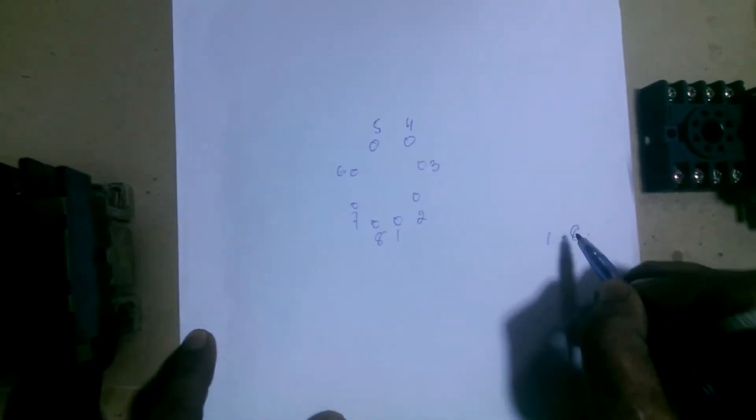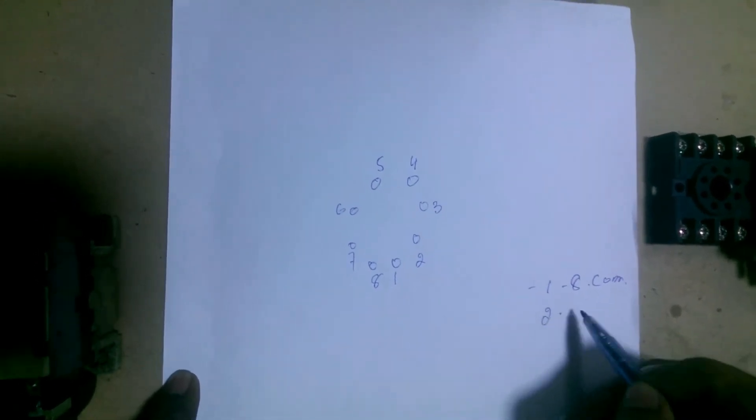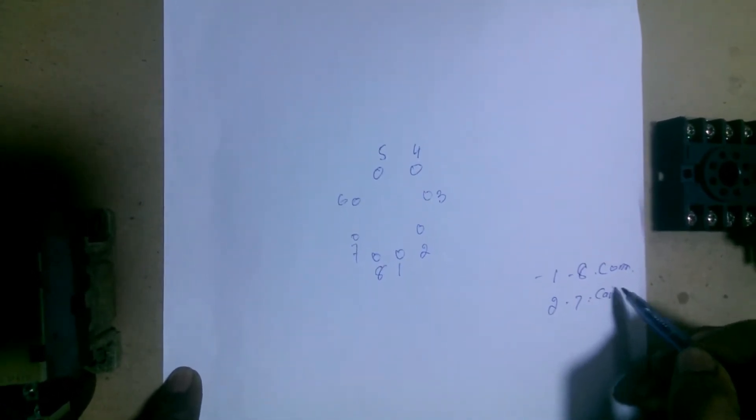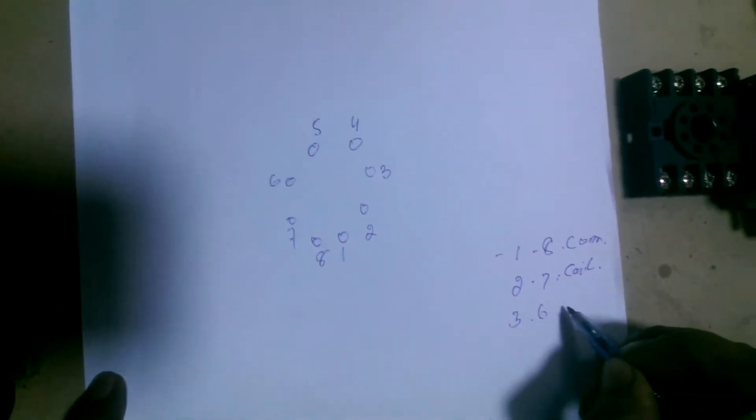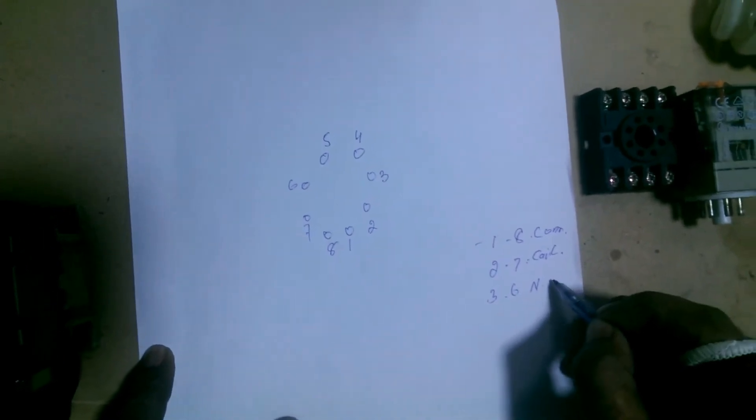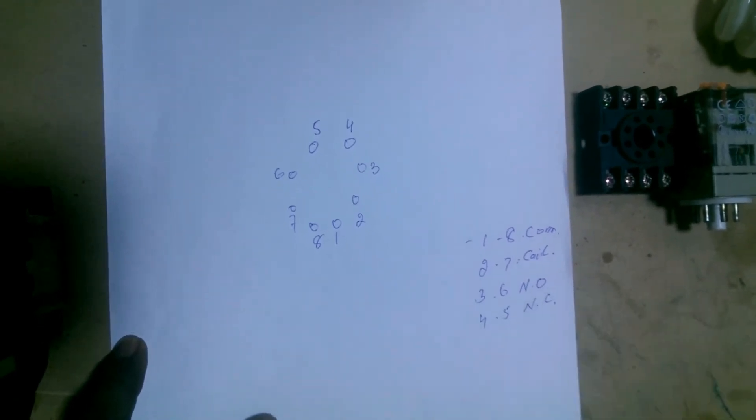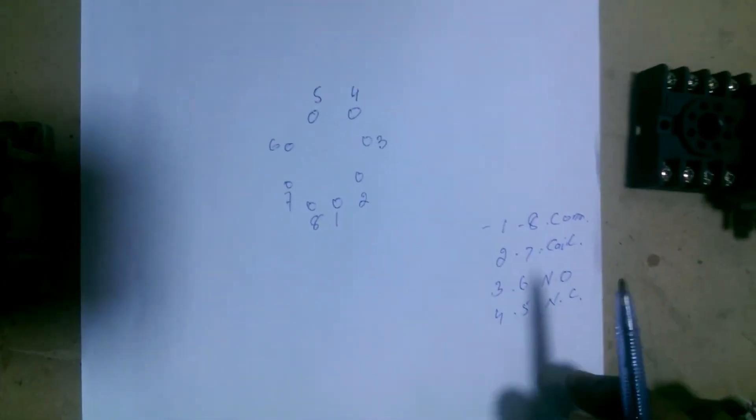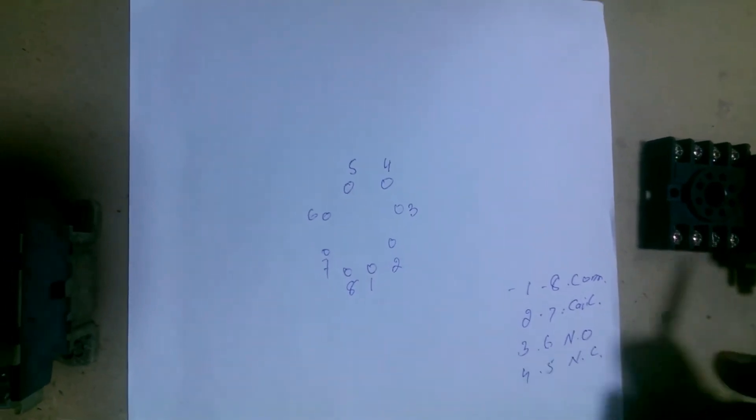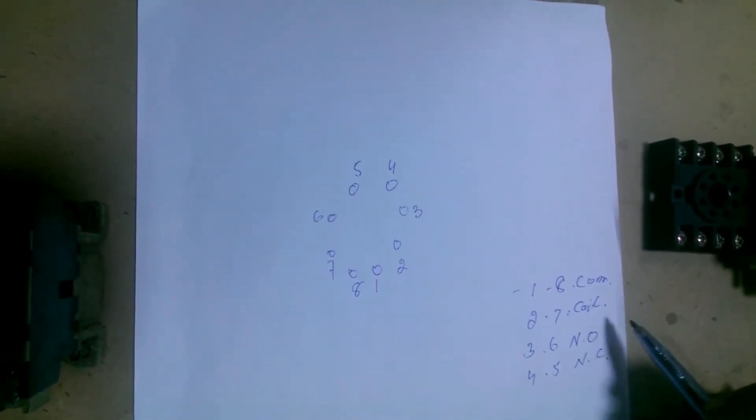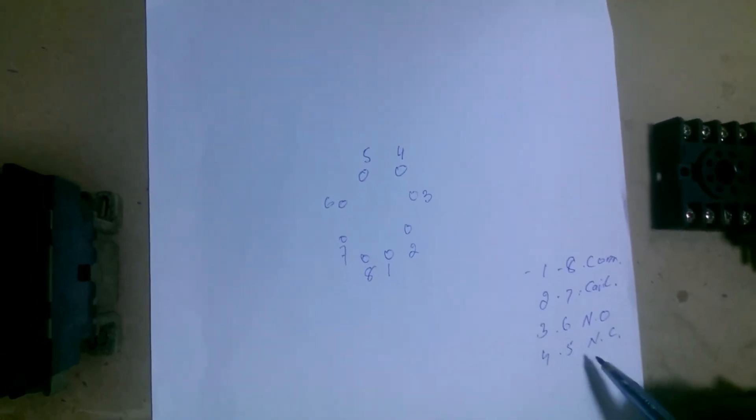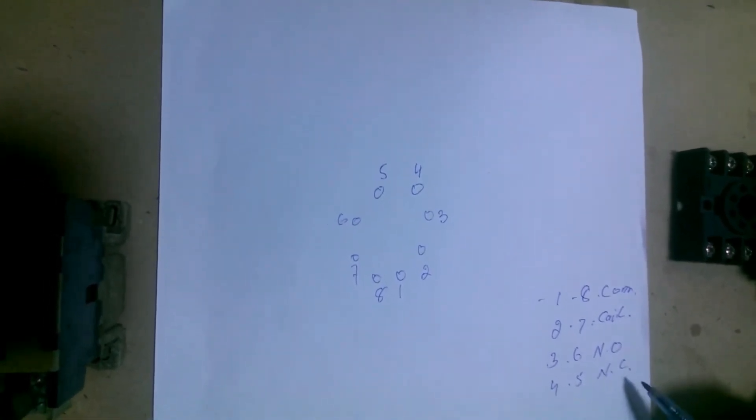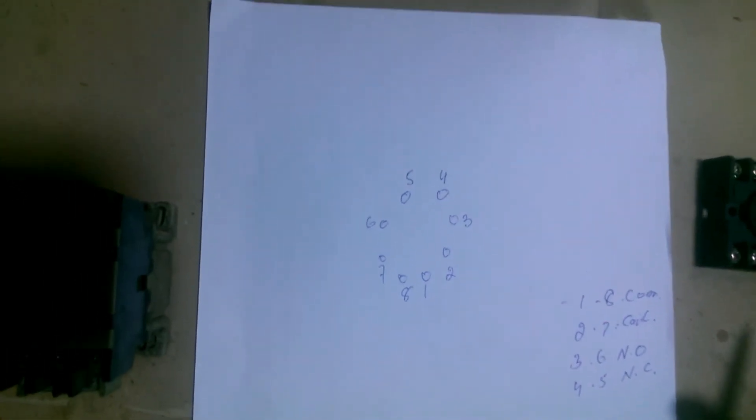Point 1 and 8 is the common. And 2 or 7 of these points are for the coil. 3 or 6 are your normally open points, NO. Meaning 4 or 5 of these two points are NC. Friends, this means that when we turn on the coil, your 3 and 6, which are normally open, they will close with 1 and 8, giving current to 1 or 8. And 4 and 5, which are normally NC, in the closed state when the coil is not on, they are closed with it.